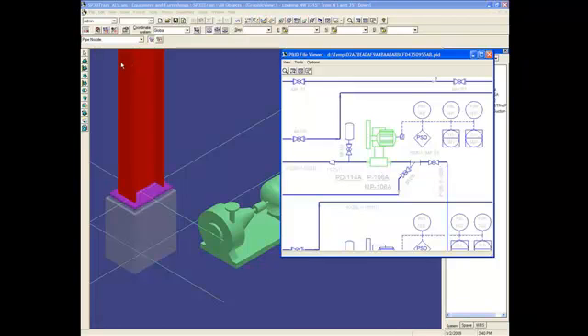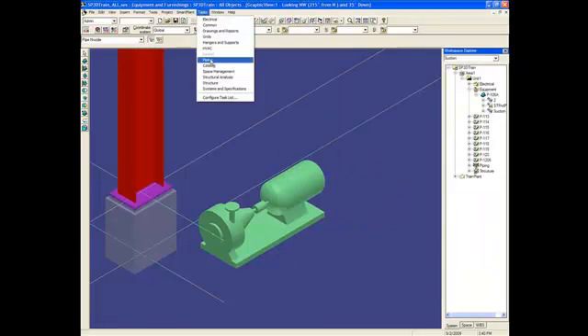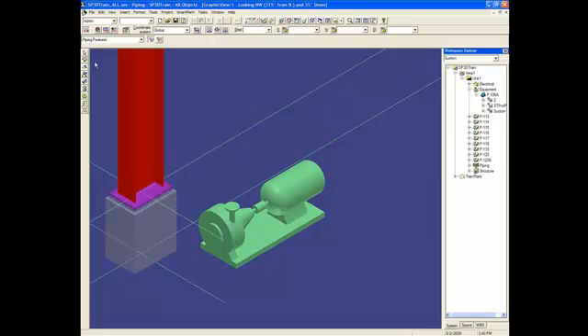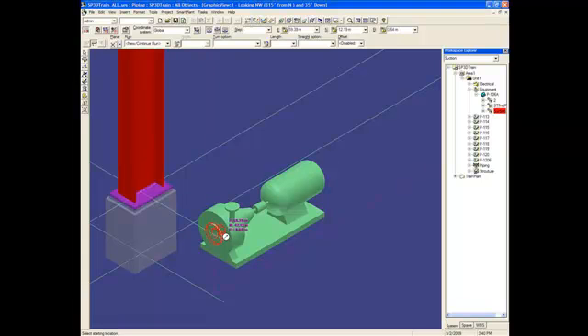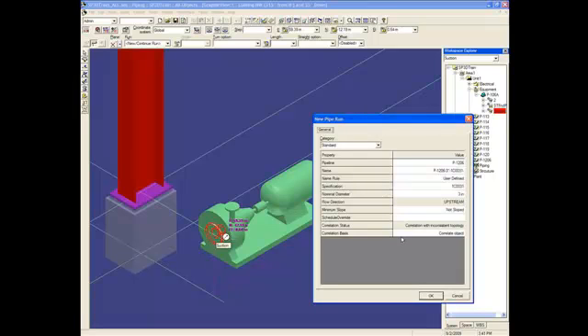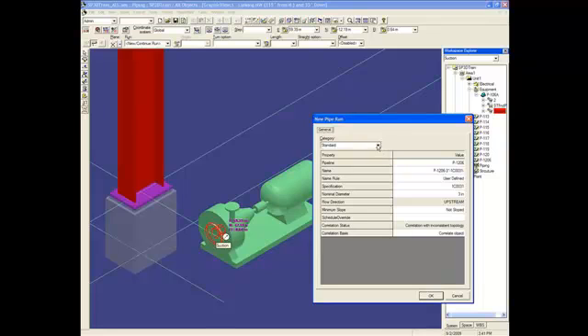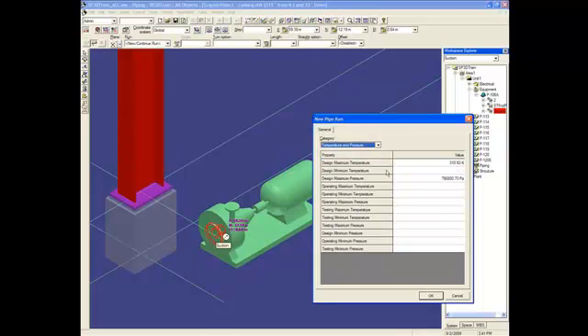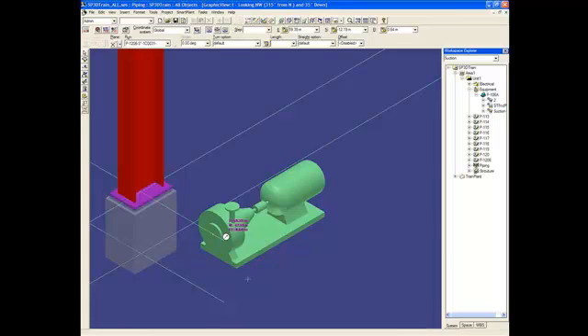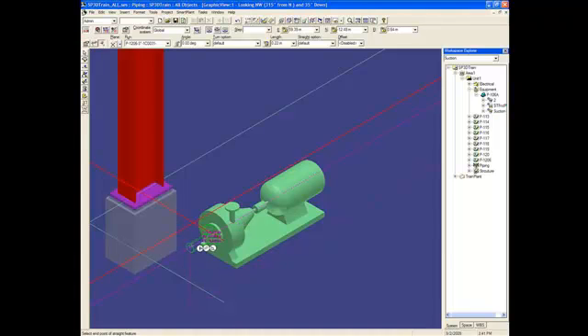Let's now start routing a pipe. So I am going to switch to my piping task. And we will route the suction of the pump. I will just start routing. I select my start point. And it knows I want to route from the P&ID because this equipment is correlated to the P&ID. So actually it gets all the information. The pipeline is already filling. The name. The spec. The diameter. If we go to temperature and pressure, the temperature and pressure are coming from the P&ID as well. So I click OK. And I start my routing.